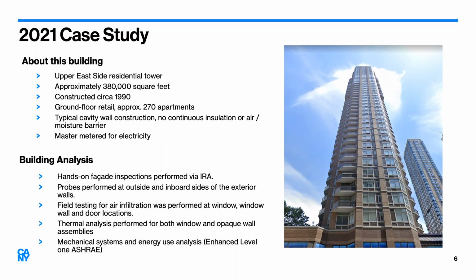Another key thing is that we actually tested the window assemblies. We didn't want to make assumptions about how the windows were performing. These are 30-year-old horizontal sliders and window wall. We got out there with a testing agency, Building Envelope Testing LLC, did air infiltration testing for us, as well as analyzed the existing frames and the glass and glazing to determine the U-values needed for our model accuracy, and the solar heat gain coefficients, showing how much load the building envelope imposes on the mechanical systems. In this building too, we had some leakage conditions we were dealing with.